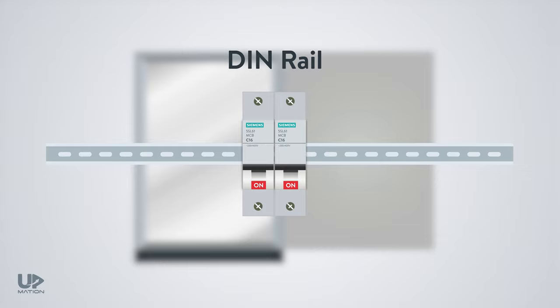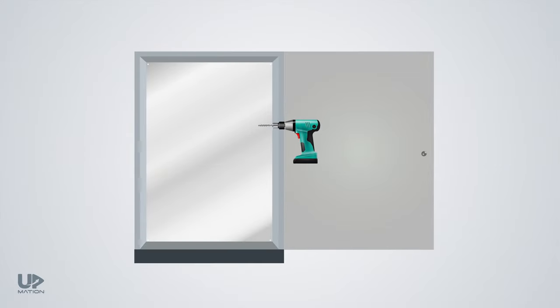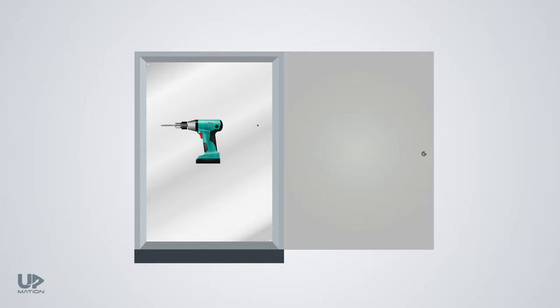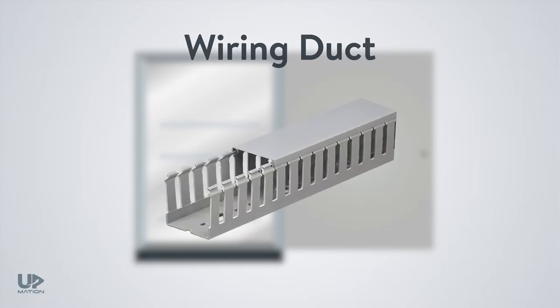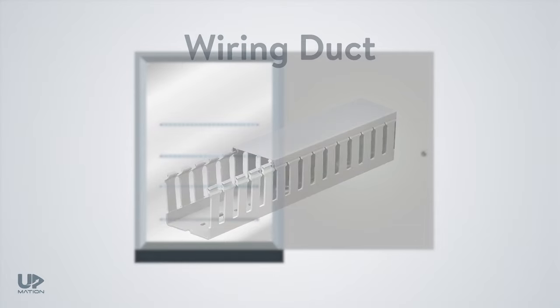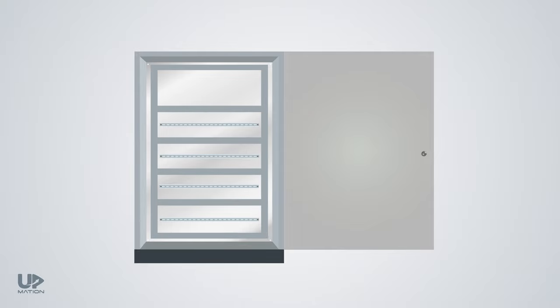In other words, instead of installing each piece of component separately, we can snap and clip the components into place easily. So we cut and install them according to the panel design. The second piece that I'm going to install on the back panel is the wiring duct. You'll see how wiring ducts will organize and cover the wires within the panel. After we cut and install the ducts inside the panel, let's get into the electrical components of the control panel.